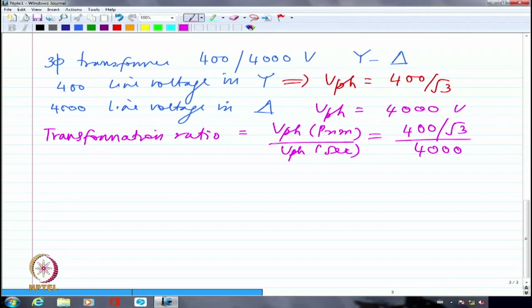We never look at line voltages directly, although specifications or nameplate details will always give line voltages, line currents, and the 3-phase kVA rating — not single-phase kVA rating. So when we draw the equivalent circuit for a 3-phase transformer, we always convert everything into a single-phase equivalent and draw the equivalent circuit in terms of that single-phase configuration.